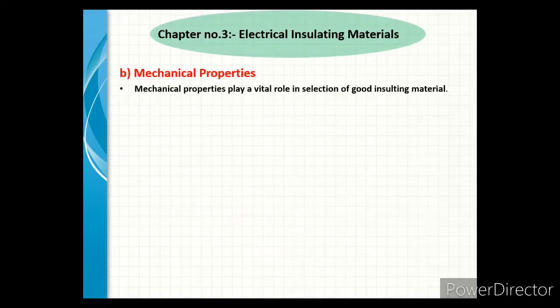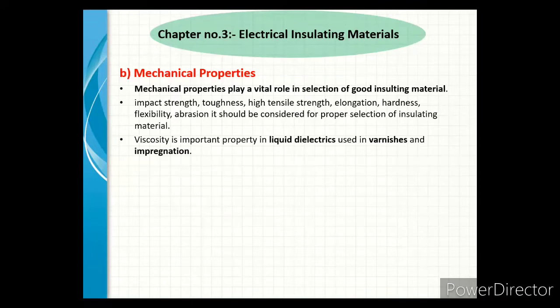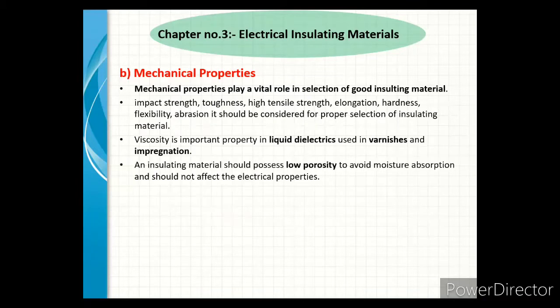Next, we see the mechanical property of insulating material. Mechanical property plays a vital role in the selection of a good insulating material. This property impacts strength, toughness, high tensile strength, elongation, hardness, flexibility, and abrasion — these should be considered for proper selection of insulating material. Viscosity is an important property in liquid dielectric used in varnishes and impregnation. An insulating material should possess low porosity to avoid moisture absorption and should not affect the electric property.